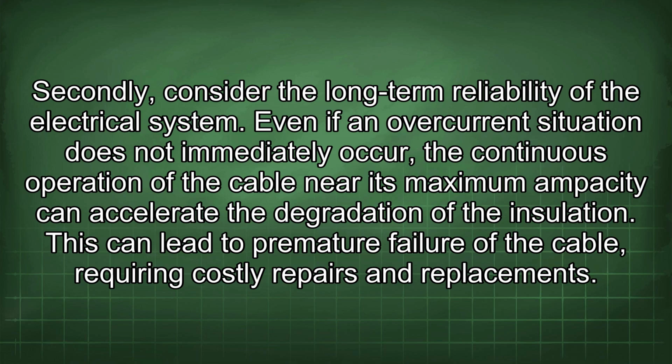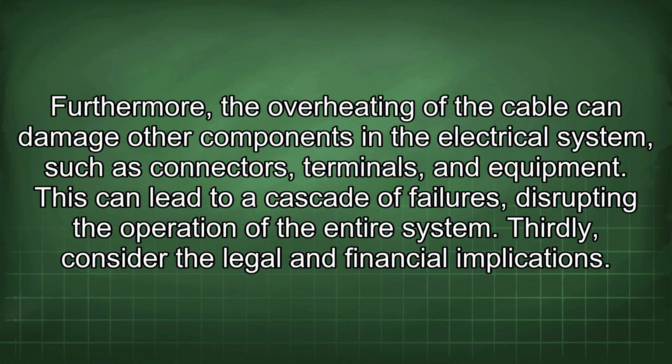Secondly, consider the long-term reliability of the electrical system. Even if an overcurrent situation does not immediately occur, the continuous operation of the cable near its maximum ampacity can accelerate the degradation of the insulation. This can lead to premature failure of the cable, requiring costly repairs and replacements. Furthermore, the overheating of the cable can damage other components in the electrical system, such as connectors, terminals, and equipment. This can lead to a cascade of failures, disrupting the operation of the entire system.